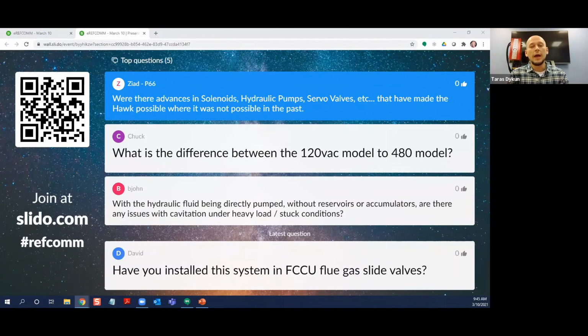Well, now we have developed technology in solenoid valves which is able to control and operate that fast. So whenever you reposition, you start the pump and build up the pressure, you open the solenoid valve, you reposition, and you close the valve. All of that can happen, as you can see from our testing here, in about 200 milliseconds. And so that's probably the main difference.